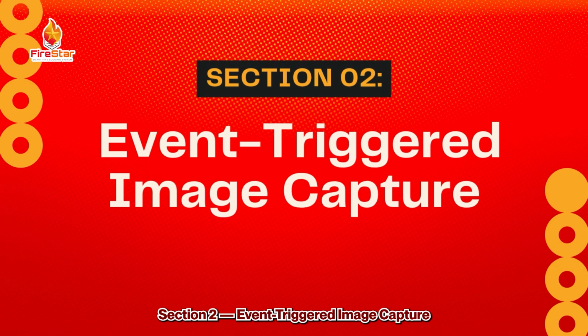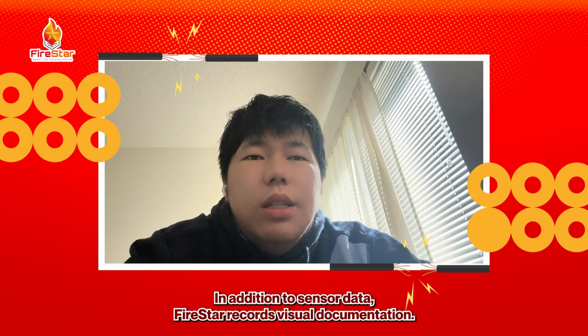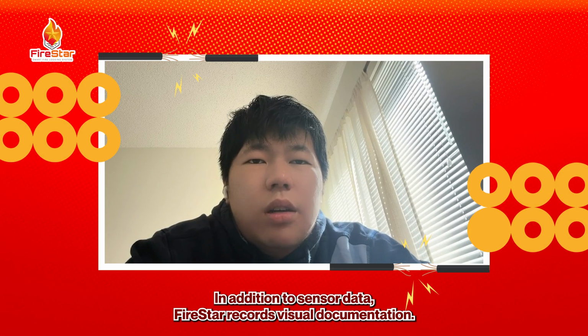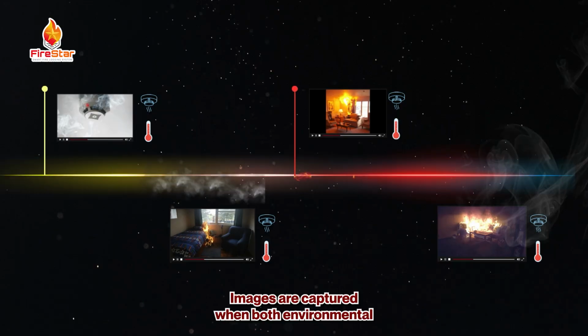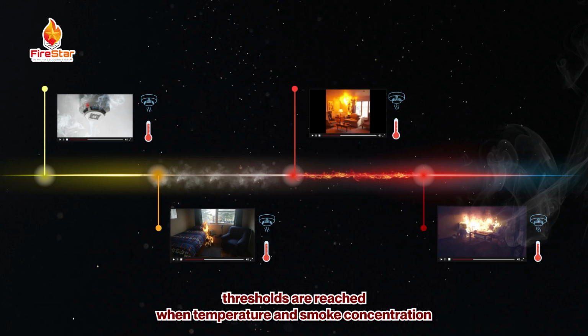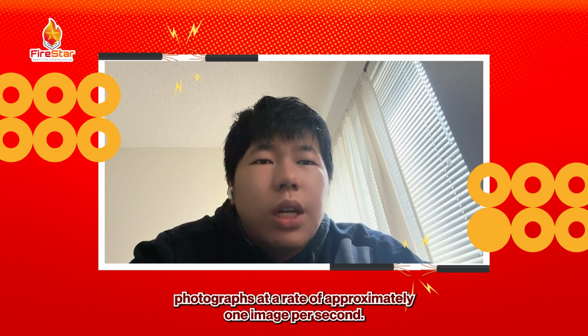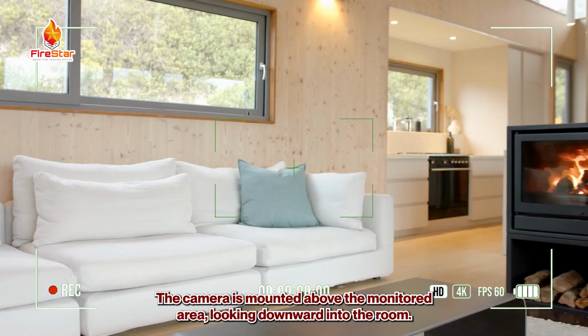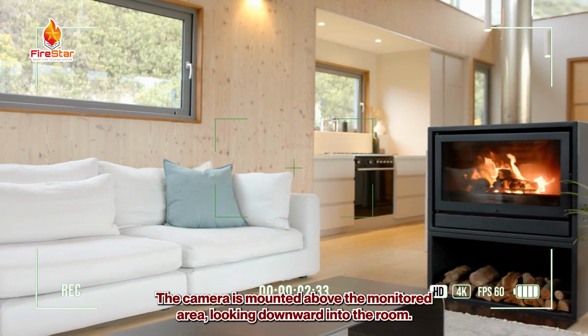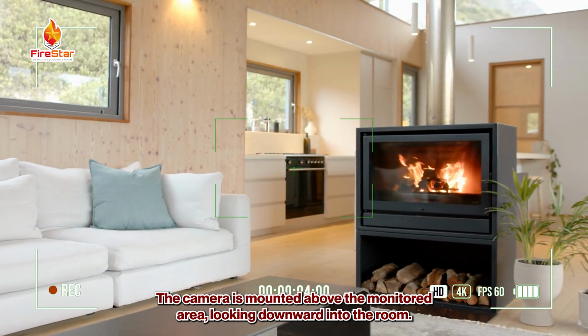Section 2. Event-triggered image capture. In addition to sensor data, FireStar records visual documentation. Images are captured when both environmental thresholds are reached, when temperature and smoke concentration rise together to levels associated with a developing fire event. Once this condition occurs, the system begins recording photographs at a rate of approximately 1 image per second. The camera is mounted above the monitored area, looking downward into the room.